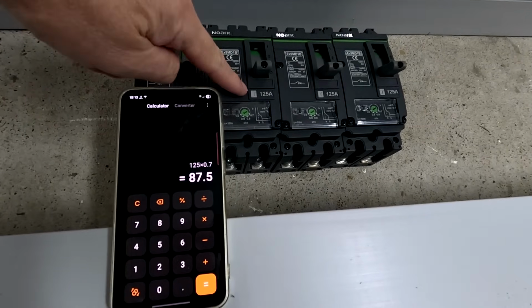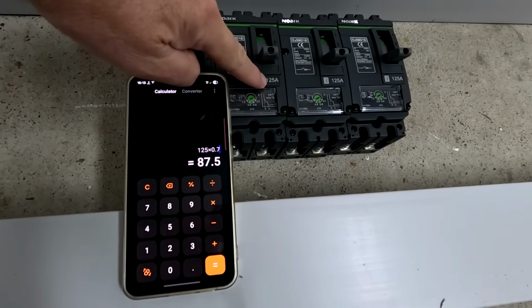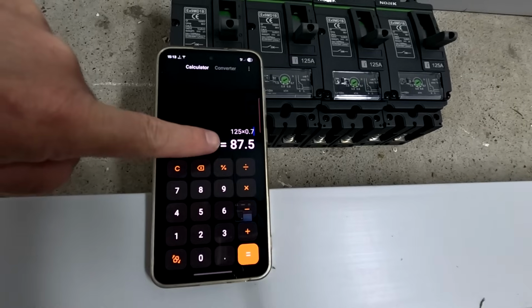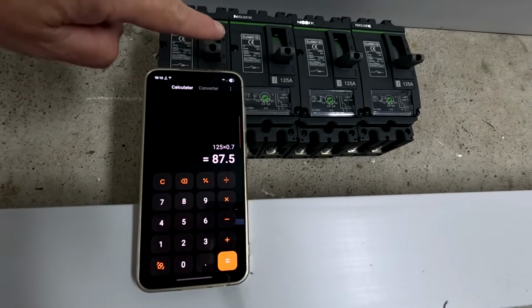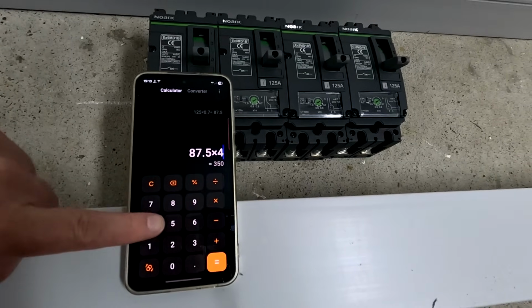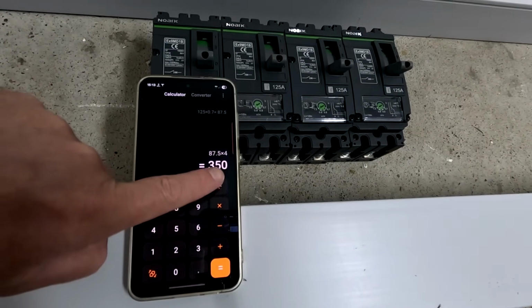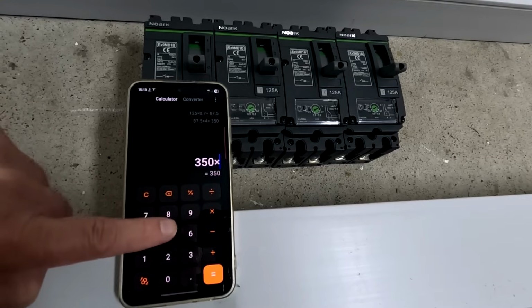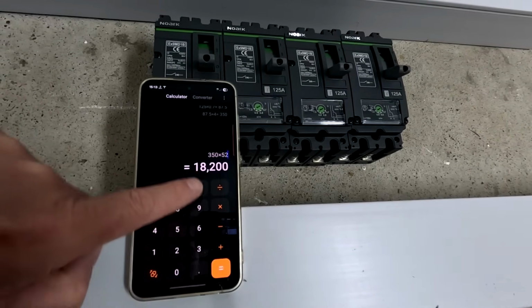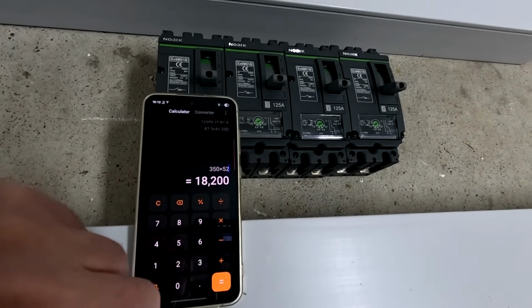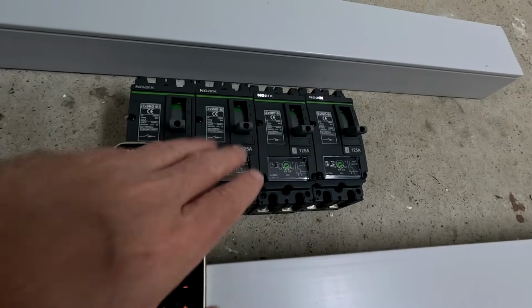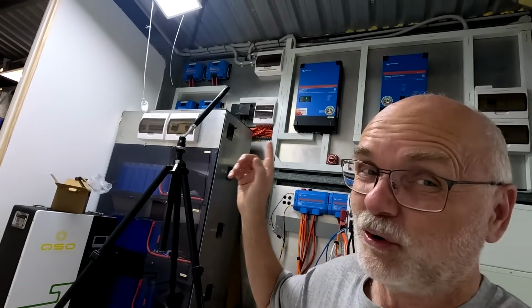So if I dial down these breakers from 125 amps to 70% of that only, it is 87.5 amps per battery, yeah? This times 4 is 350 amps all in total, times 52 volts, say. This is 18.2 kilowatts already at 70% of the capacity of these breakers. And I'm running the whole show now here from 5 kilowatt plus an additional 2 kilowatt if I need it. So 18.2. Who needs that much power?